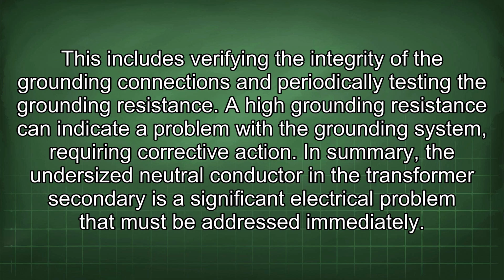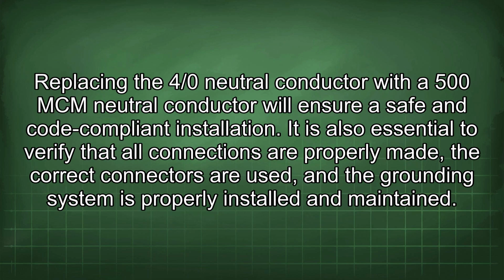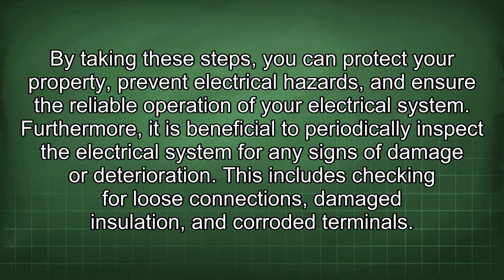In summary, the undersized neutral conductor in the transformer secondary is a significant electrical problem that must be addressed immediately. Replacing the 4/0 neutral conductor with a 500 MCM neutral conductor will ensure a safe and code-compliant installation. It is also essential to verify that all connections are properly made, the correct connectors are used, and the grounding system is properly installed and maintained. By taking these steps, you can protect your property, prevent electrical hazards, and ensure the reliable operation of your electrical system.